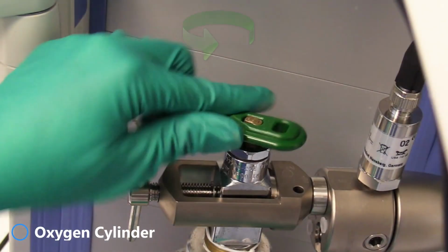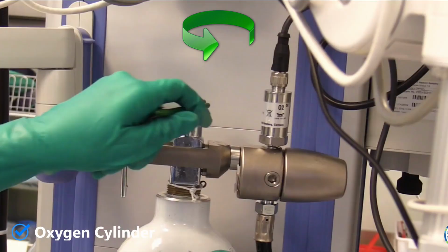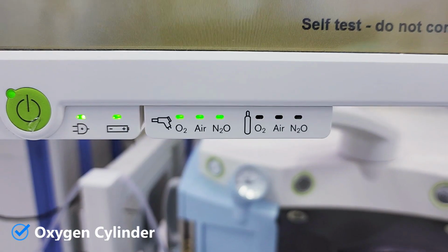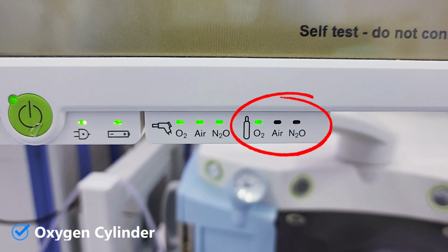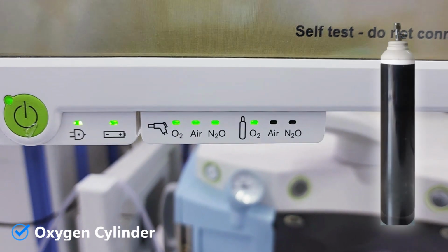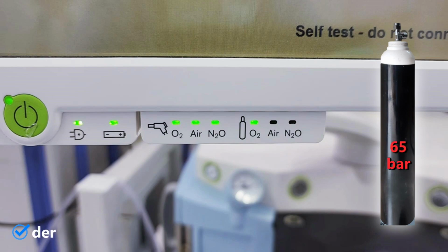To check the oxygen cylinder, turn the cylinder valve anticlockwise. The LED indicators should be green. The cylinder pressure can be seen from the test info page. A full oxygen cylinder size E will read 137 bar. The oxygen cylinder has to be changed if the pressure goes down below half.